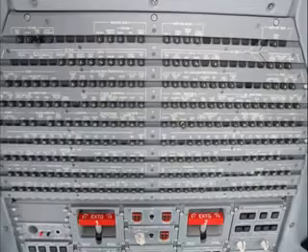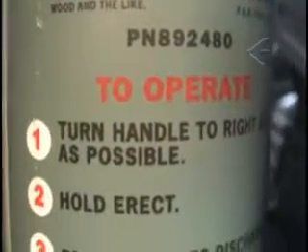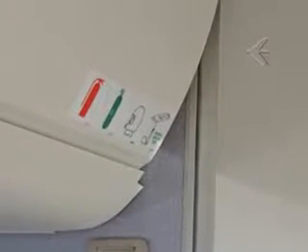The water fire extinguisher is more effective than Halon against paper, wood, fabric, or rubber, Class A fire. However, the water fire extinguisher should not be sprayed directly into a CB panel or an electrical outlet, nor should it be used on grease or fuel. Water extinguisher use is acceptable if the surface has absorbed the liquid, such as gasoline poured on a seat.